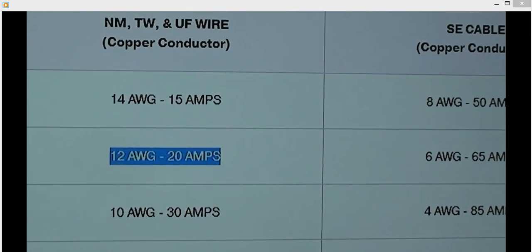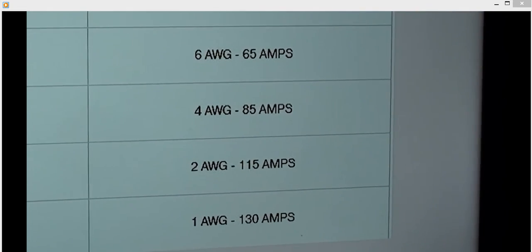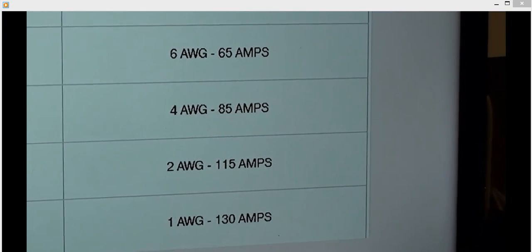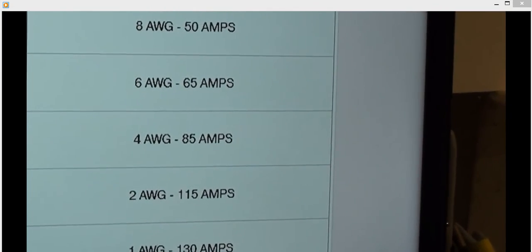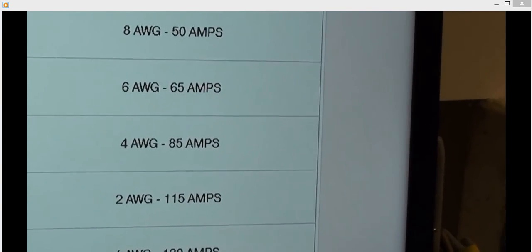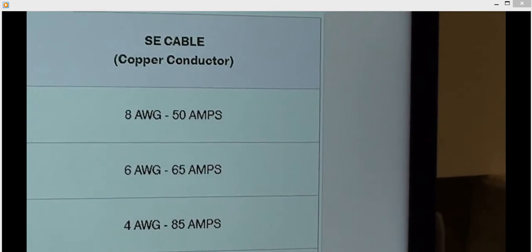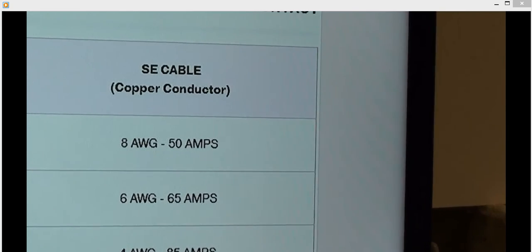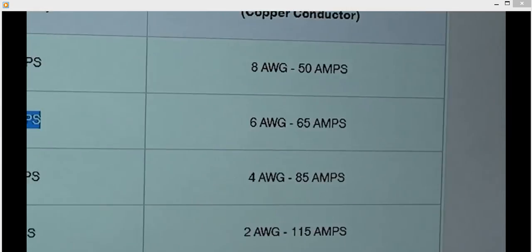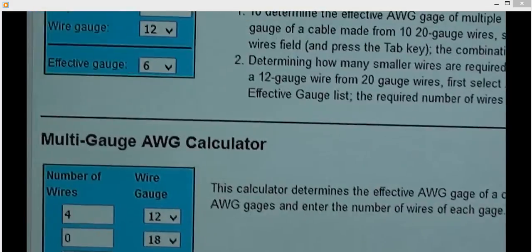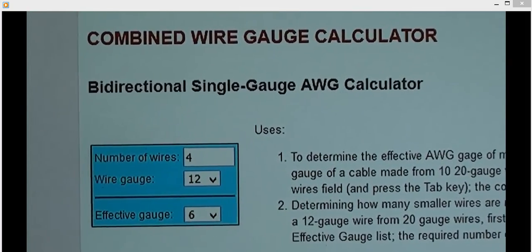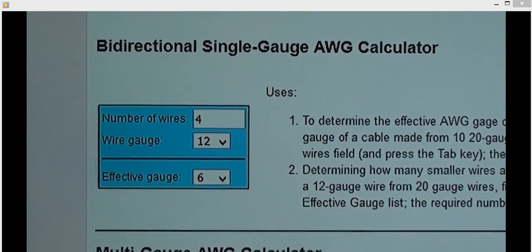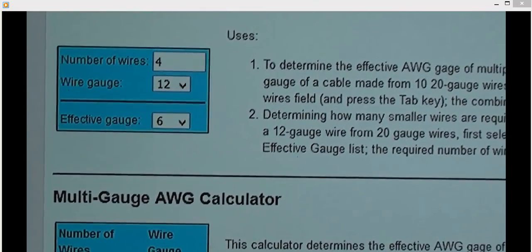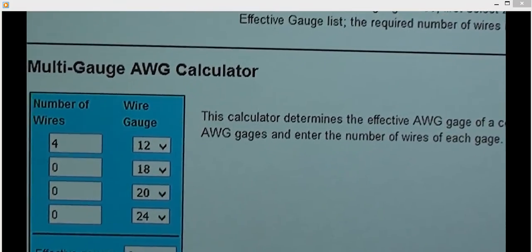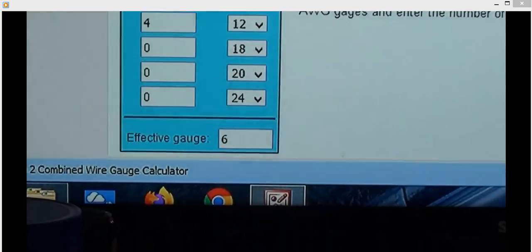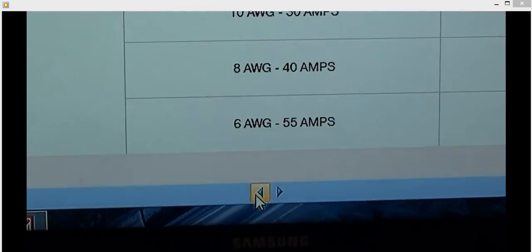Now for this to work, you would need 4 AWG 85 amps, because that would give you 340 amps. Because the 4 65s only give you 260 amps. So if we look over here, at the combined wire gauge calculator, it says 4 wires of 12 gauge equals an effective gauge of 6 gauge. A 6 gauge wire is only equal to 55 amps.